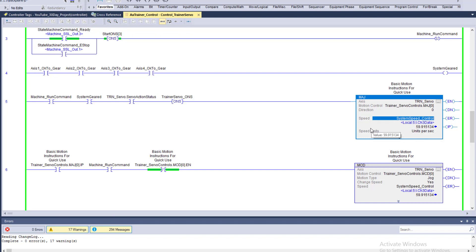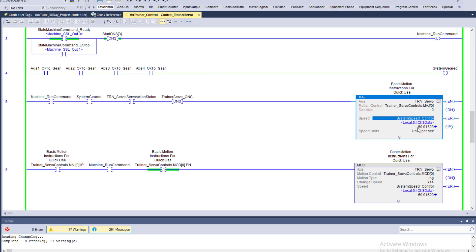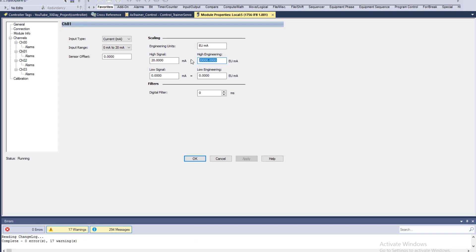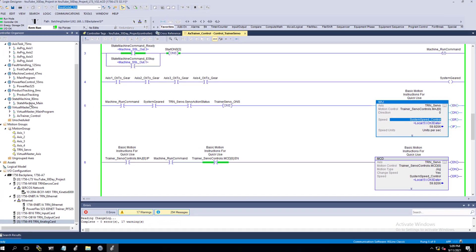I'm using this as a speed reference, zero to 60 as in Hertz, in a servo trainer setup. At the maximum of the speed pot I'm getting 60, and at the minimum I'm getting zero. You may have your engineering units set to milliamps scaled to 20,000, or zero — there are many different ways to scale things based upon your situation. This gives you a base understanding of how it's scaled and how it could be used on many different platforms.